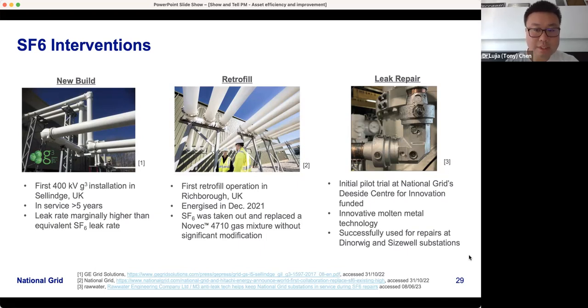The last one is leak repair. The key thing to remember with retrofill is the costing is mainly just the gas and the labor, so the cost is only a few million rather than in excess of tens of millions or even over 100 million. But retrofill doesn't work on all legacy equipment because there are compatibility issues - at the end of the day, we're putting a new gas into equipment that's optimized for SF6, so certain equipment will end up being too leaky to trial the retrofit solution.